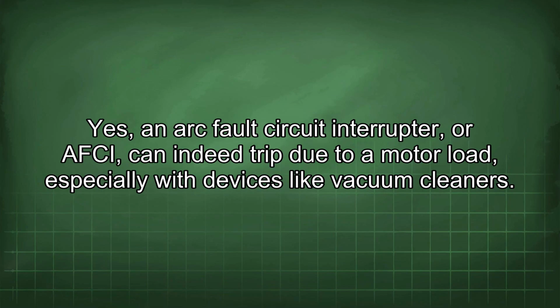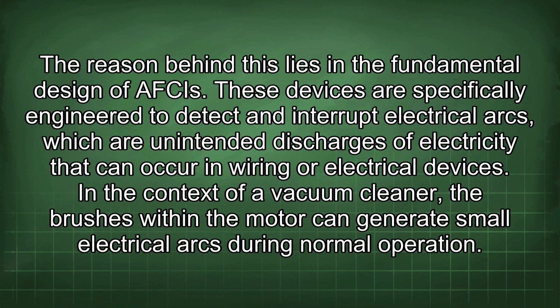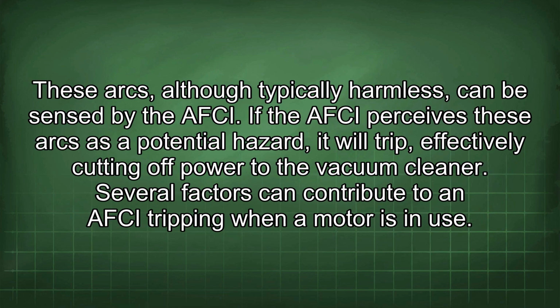Yes, an arc fault circuit interrupter, or AFCI, can indeed trip due to motor load, especially with devices like vacuum cleaners. The reason behind this lies in the fundamental design of AFCIs. These devices are specifically engineered to detect and interrupt electrical arcs, which are unintended discharges of electricity that can occur in wiring or electrical devices. In the context of a vacuum cleaner, the brushes within the motor can generate small electrical arcs during normal operation. These arcs, although typically harmless, can be sensed by the AFCI. If the AFCI perceives these arcs as a potential hazard, it will trip, effectively cutting off power to the vacuum cleaner.